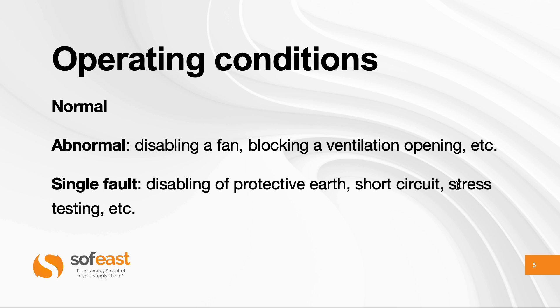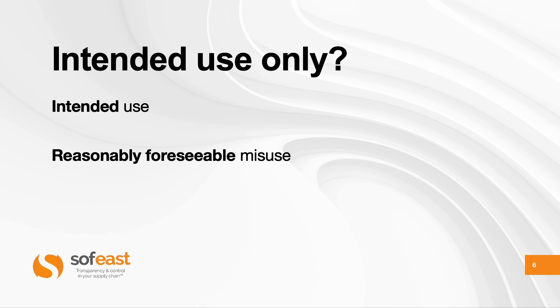A single fault condition means, for example, protective earth is disabled or there's a short circuit. These are examples of single fault. Also, when a product is being stress tested in a lab — a hipot test or something like that — this is usually a single fault condition. It can occur in a lab or out in the hands of users.